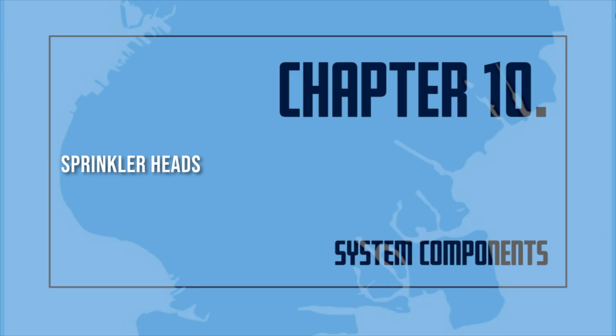Sprinkler heads exposed to corrosive conditions are often covered with a protective coat of wax or lead. Corrosive vapors are likely to make automatic sprinklers inoperative or slow down the speed of operation. They can also seriously block the spray nozzles in the sprinkler heads. They can damage, weaken or destroy the delicate parts of the sprinkler heads. In most cases, such corrosive action takes place over a long time. For this reason, the sprinkler heads must be carefully watched for signs of corrosion. Care should be taken to make sure that the protective coating is not damaged when handling or replacing the heads.